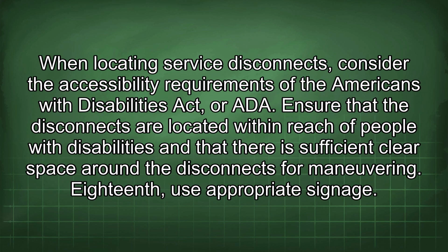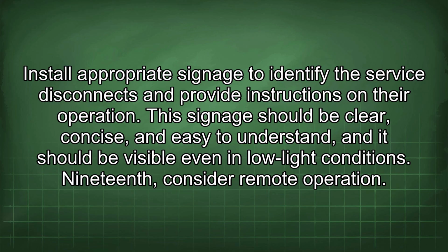17th, consider accessibility for people with disabilities. When locating service disconnects, consider the accessibility requirements of the Americans with Disabilities Act, or ADA. Ensure that the disconnects are located within reach of people with disabilities and that there is sufficient clear space around the disconnects for maneuvering. 18th, use appropriate signage. Install appropriate signage to identify the service disconnects and provide instructions on their operation. This signage should be clear, concise, and easy to understand, and it should be visible even in low light conditions.